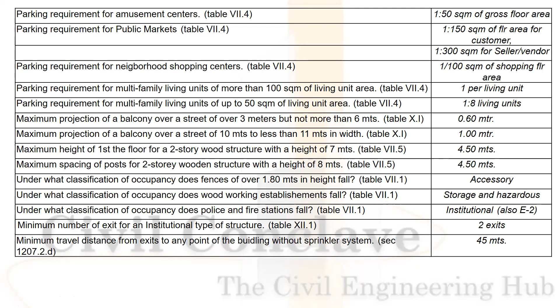Spacing of the posts of the two-storey wooden structure, 4.5 meters. Minimum number of exits for an institutional structure will be 2 exits. Maximum travel distance from exit point without a sprinkler will be 45 meters. Maximum traveling distance from any point with a sprinkler system will be 60 meters. A long interior passageway is known as a corridor.